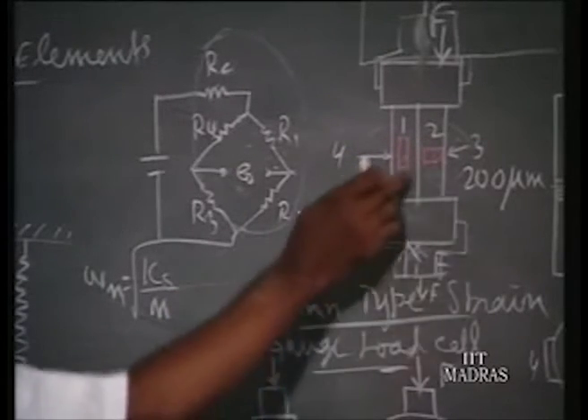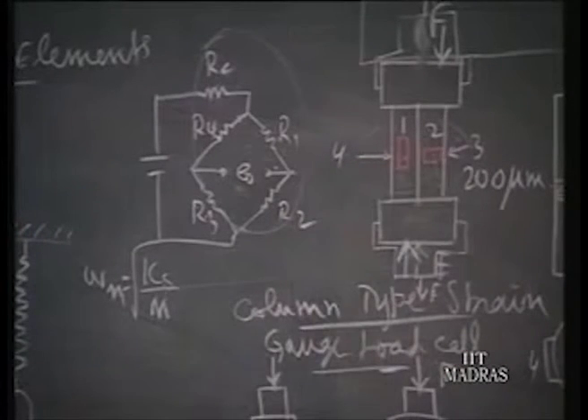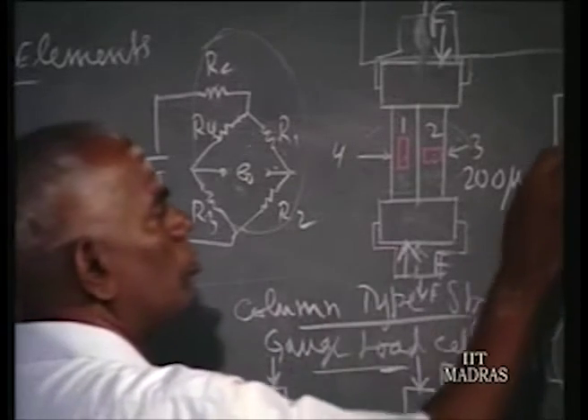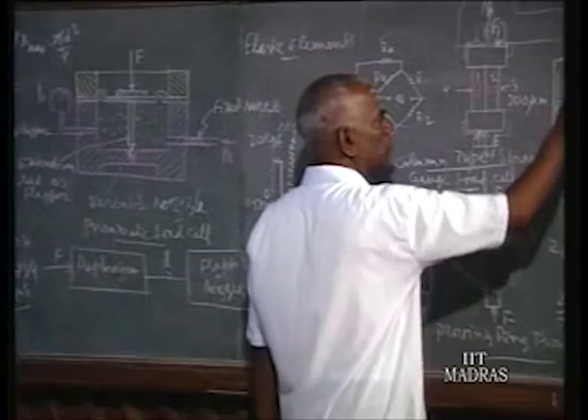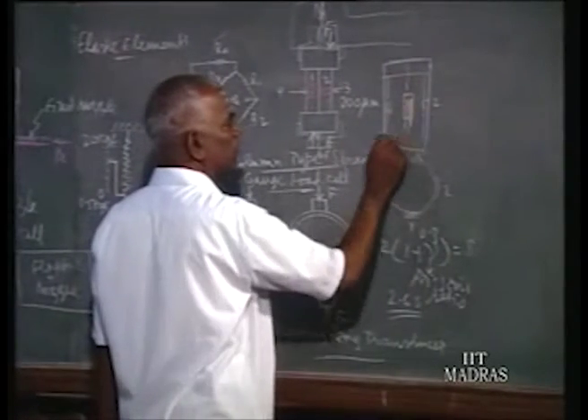To increase sensitivity, one disadvantage is that when we reduce the cross section, it becomes too narrow, or you may have a very small area for the strain gauges. To avoid the problem, what people do is have a hollow construction at the place where we want to fix the strain gauges.